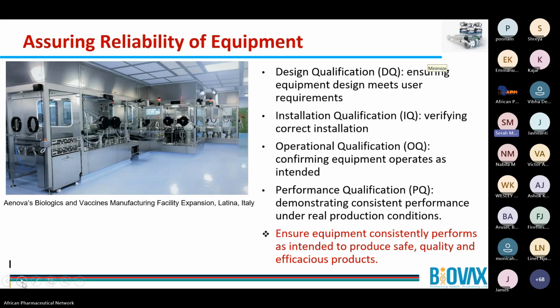Then you have the installation qualification to verify the installation is correct. Then we have the operation qualification to confirm that the equipment operates as intended. And then the most important is the performance qualification, which demonstrates consistent performance under real production conditions. So during the performance qualification, you have to have the product. And the protocol itself will have the specifications. And by the time you're done, you should have a certificate to demonstrate that the equipment has performed as it should.